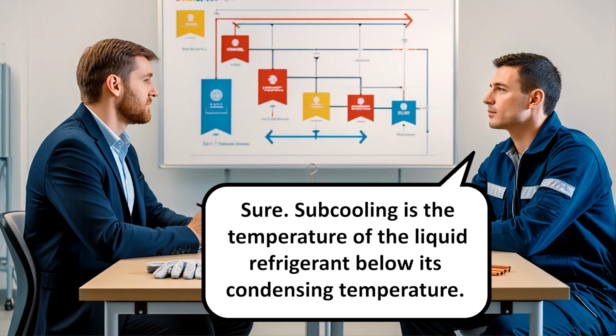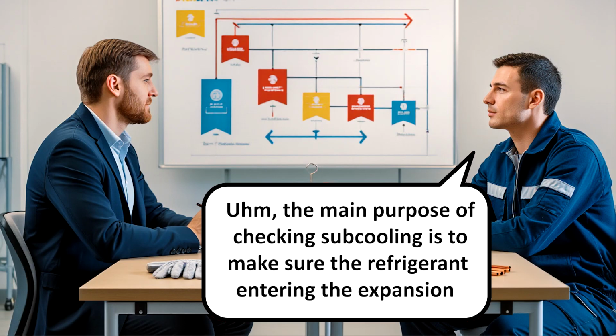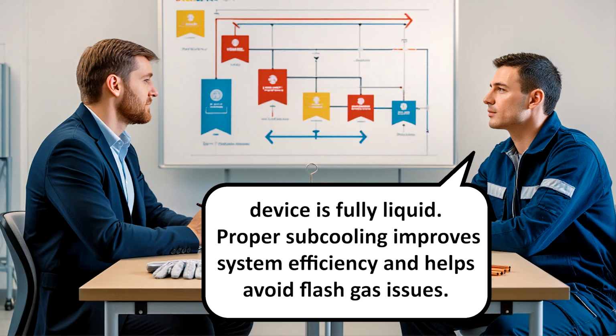Good. And could you also explain what subcooling is? Sure. Subcooling is the temperature of the liquid refrigerant below its condensing temperature. The main purpose of checking subcooling is to make sure the refrigerant entering the expansion device is fully liquid. Proper subcooling improves system efficiency and helps avoid flash gas issues.